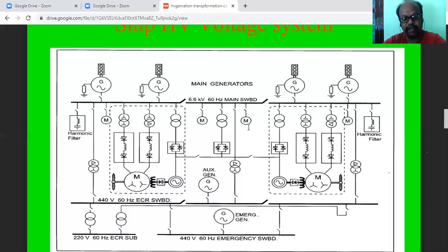But even after that, it will keep on moving because of the water flow. The propeller will keep on rotating. At that time, because the DC excitation is there, this will be acting as a generator. So that power can be fed back to the source, where we are able to use it for many other motors, or even I can take it for the 220 volt system. If I provide a further rectifier and battery arrangement, we are able to store that. That is why there are two different converters.